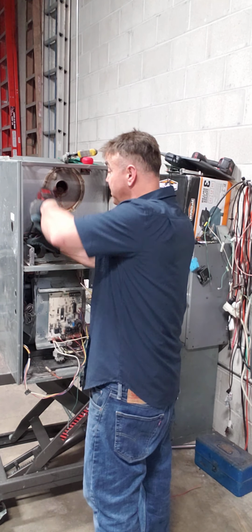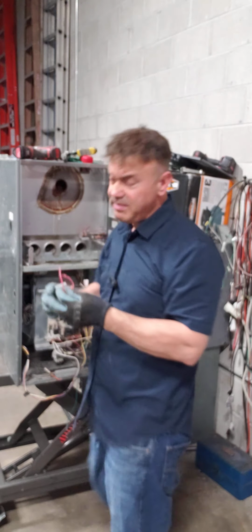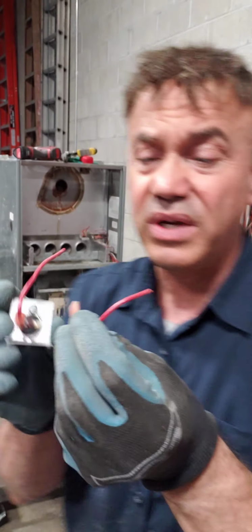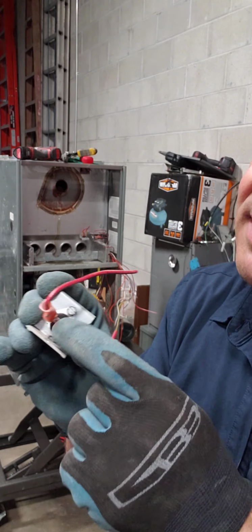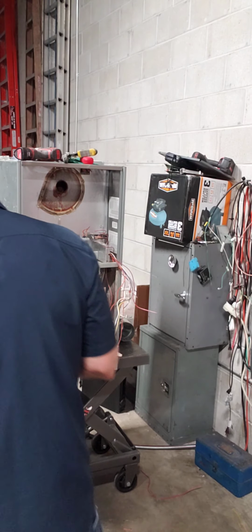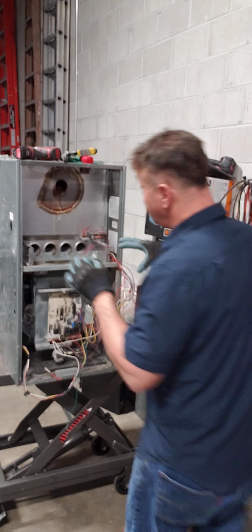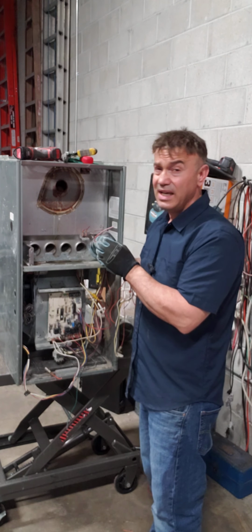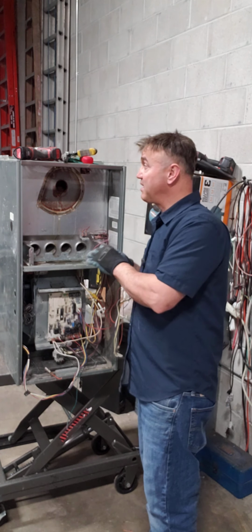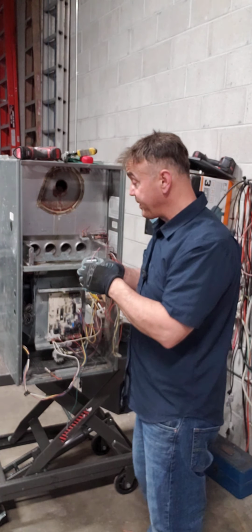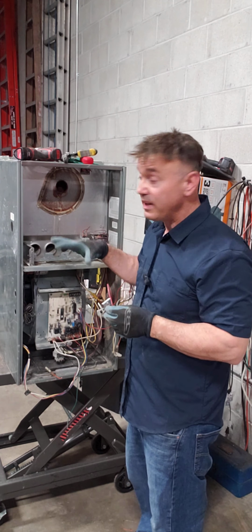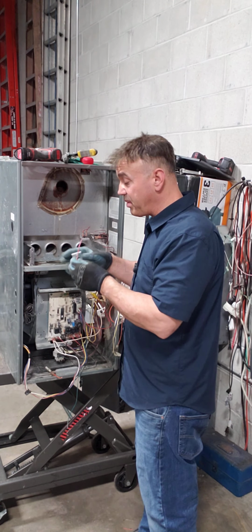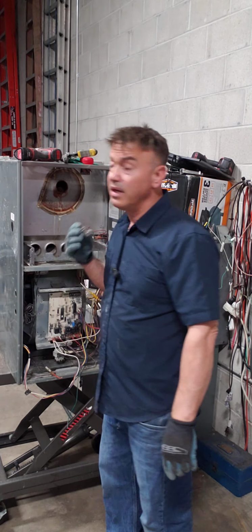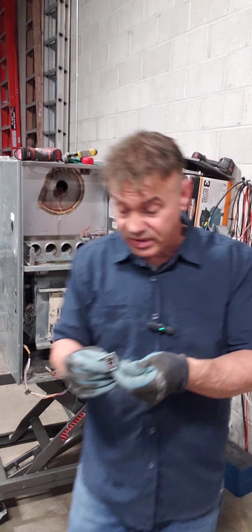Okay, so these are the limit switches. As you see, the limit switch has, I broke it, don't do like me, it has like a reset switch. So basically, the rollout switch monitors the burner's compartment, to make sure the flame is being sucked immediately into the heat exchanger and shot out. So anytime something slows that flow, the burner's compartment will become overheated, and sometimes you can see it on this limit switch, if you clean it very well here.